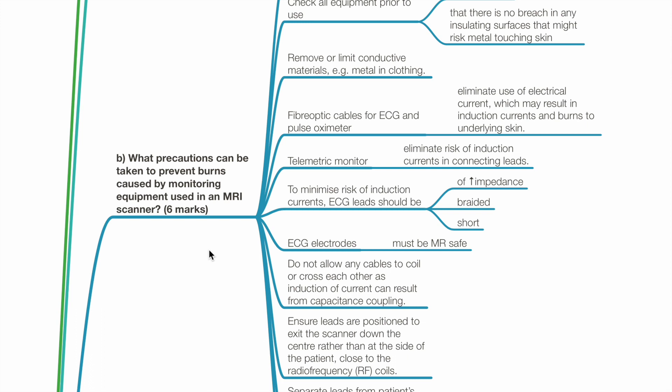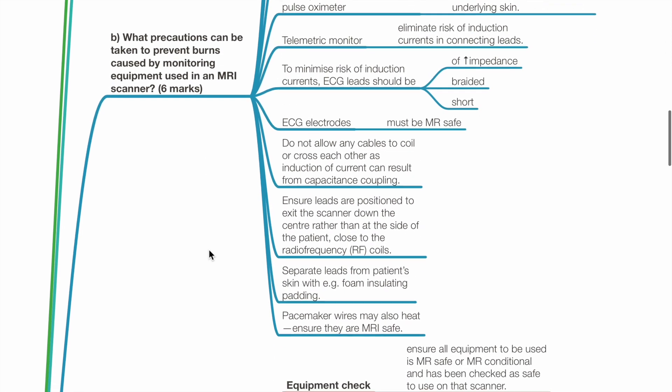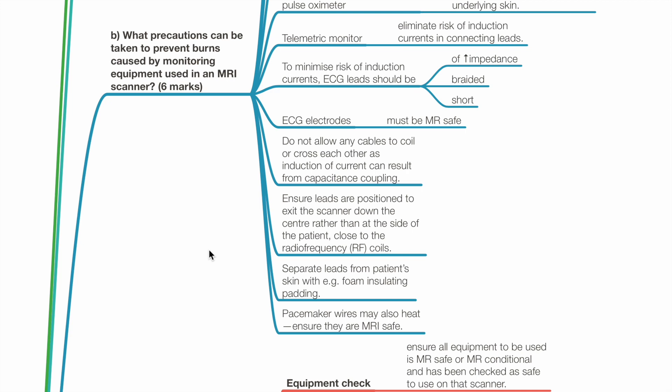To minimize the risk of induction currents, ECG leads should be of high impedance, braided, and short. ECG electrodes must be MR-safe. Do not allow any cables to coil or cross each other, as induction of current can result from capacitance coupling.